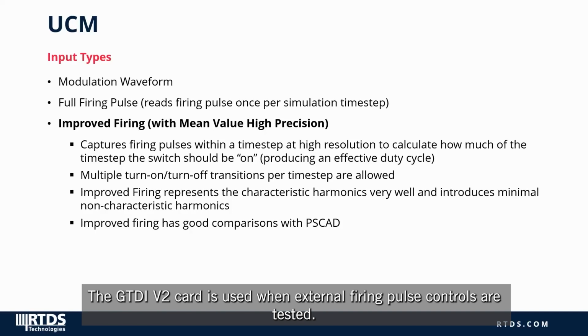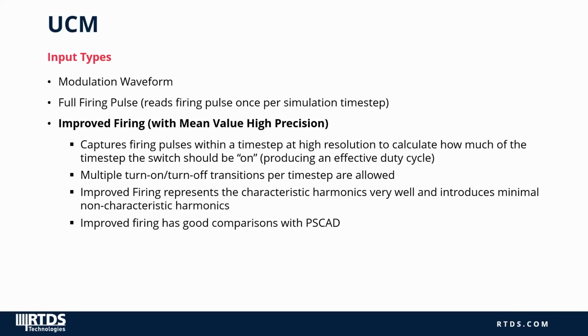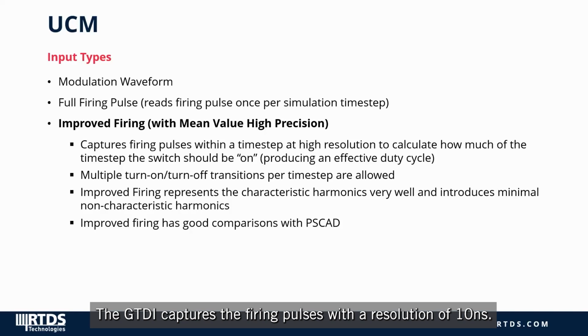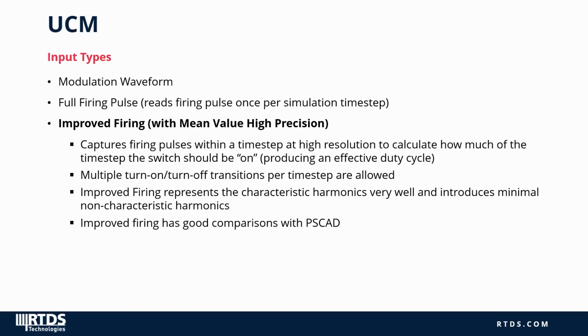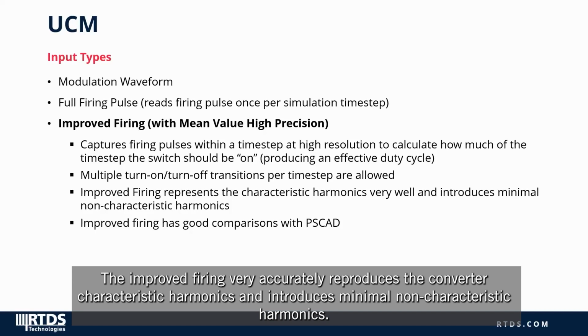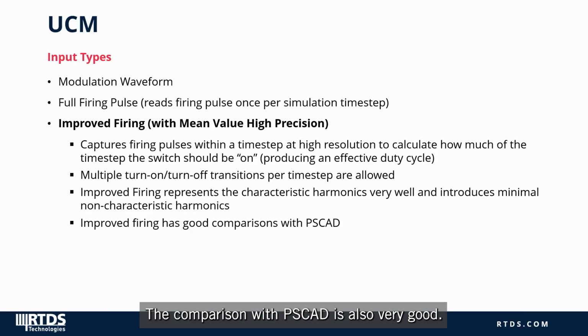The GTDI V2 card is used when external firing pulse controls are tested. The GTDI captures the firing pulses with a resolution of 10 nanoseconds. The improved firing very accurately reproduces the converter characteristic harmonics and introduces minimal non-characteristic harmonics. The comparison with PSCAD is also very good.